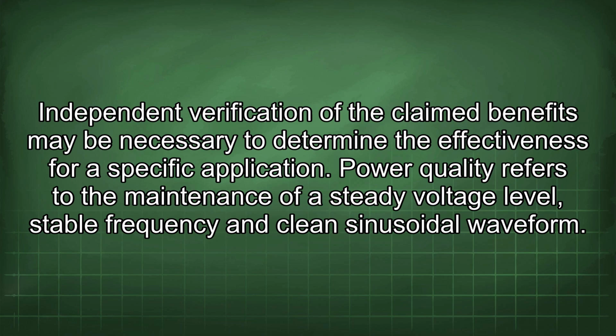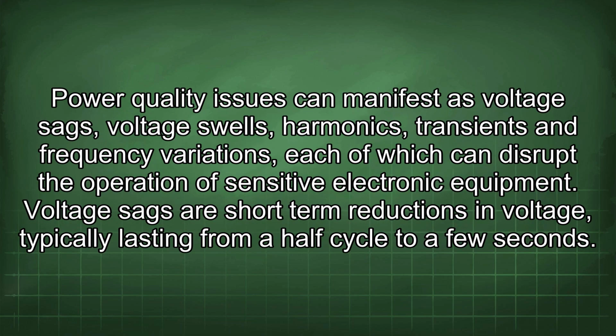Power quality refers to the maintenance of a steady voltage level, stable frequency, and clean sinusoidal waveform. Power quality issues can manifest as voltage sags, voltage swells, harmonics, transients, and frequency variations, each of which can disrupt the operation of sensitive electronic equipment.